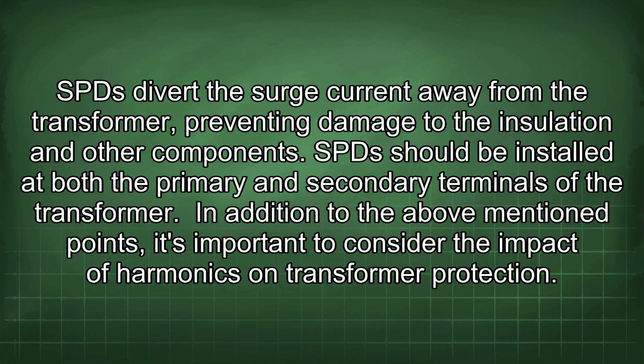SPDs divert the surge current away from the transformer, preventing damage to the insulation and other components. SPDs should be installed at both the primary and secondary terminals of the transformer. In addition to the above-mentioned points, it's important to consider the impact of harmonics on transformer protection.